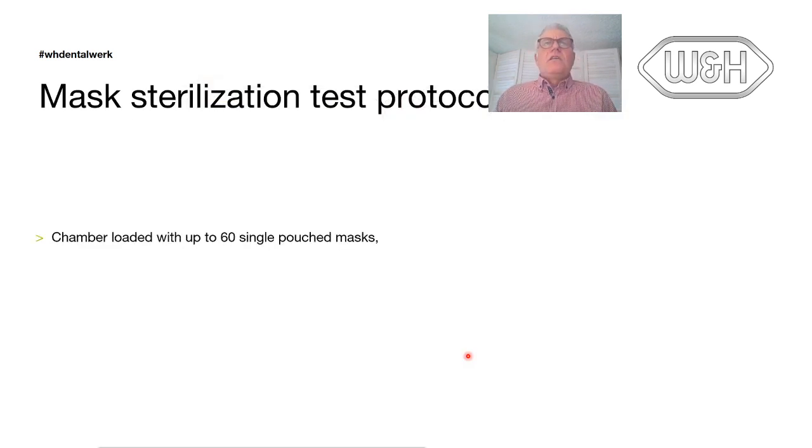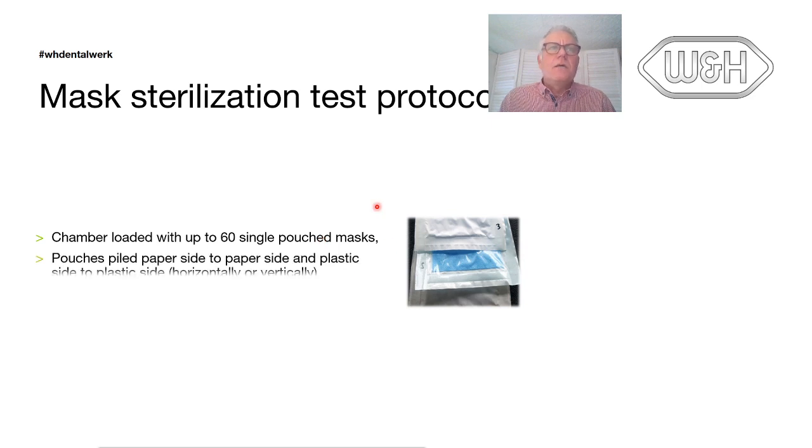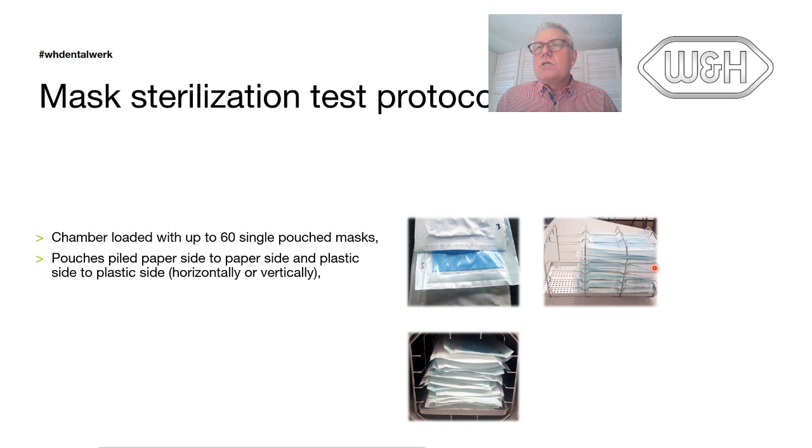Even better, if your manufacturer can test this, and this is what we have done with all our models. We have loaded as many as we could. We loaded 60 single pouch masks, so this will keep them sterile after processing. This is an unusual loading technique. This is also why it's important that you check with your manufacturer, because we supply the machines with 5 trays, and you will split the normal instruments on 5 trays. Here, because of space, we put as many as we could, and this is recognizable like a full porous load, but it's very light.